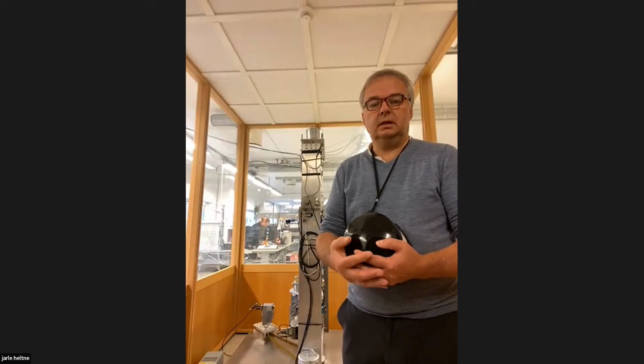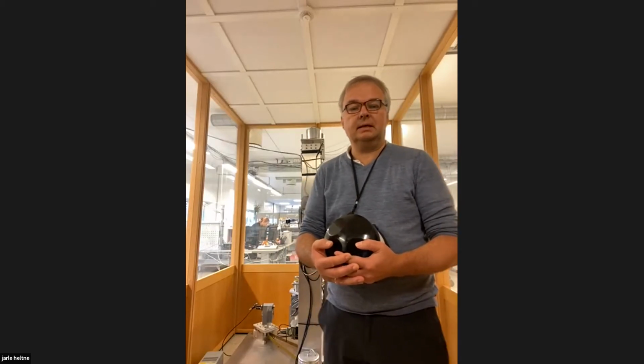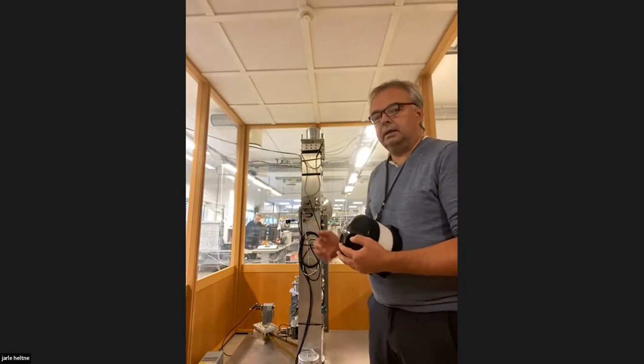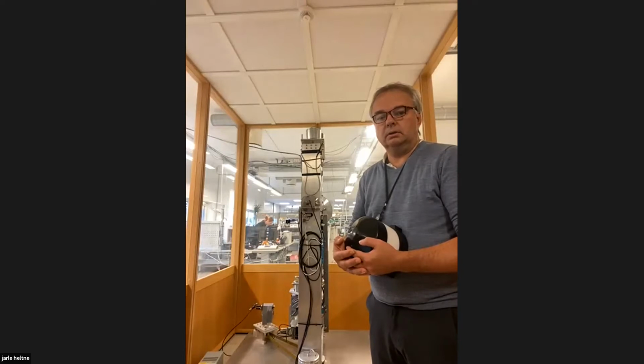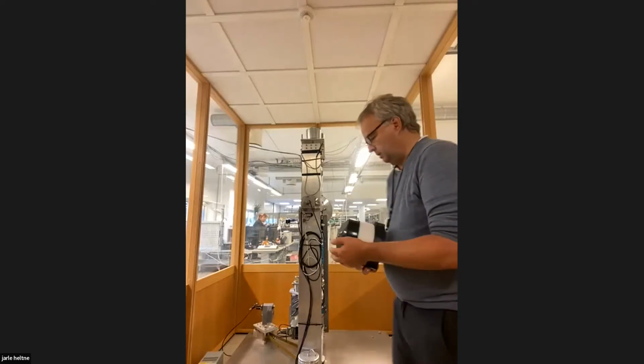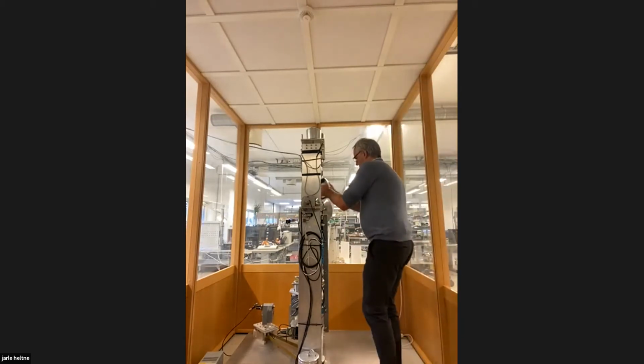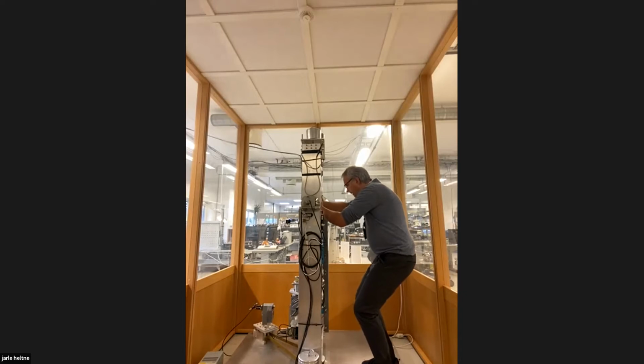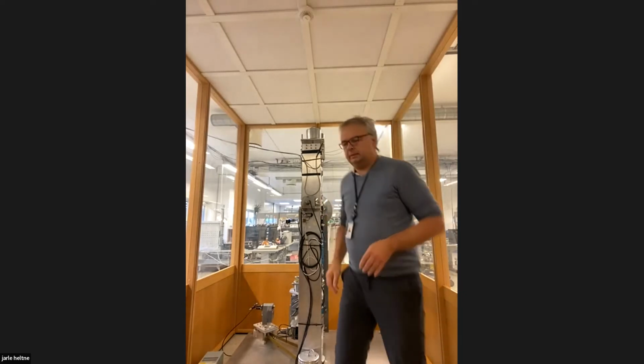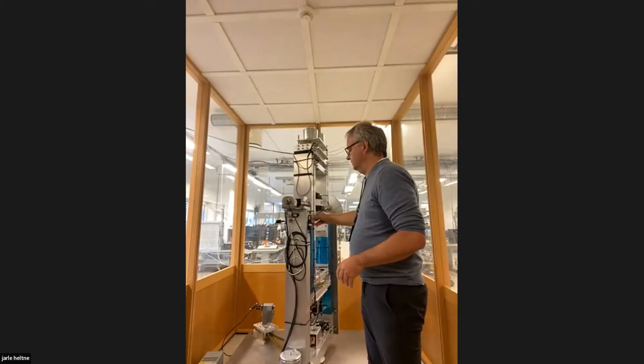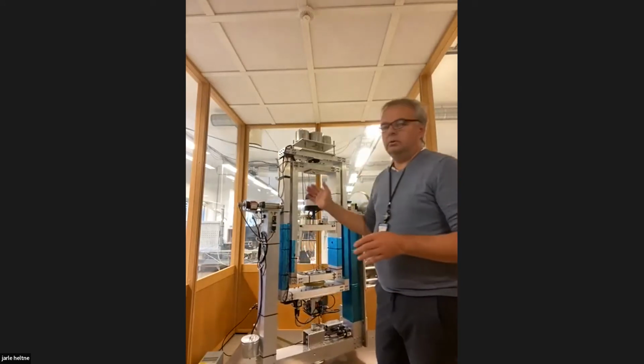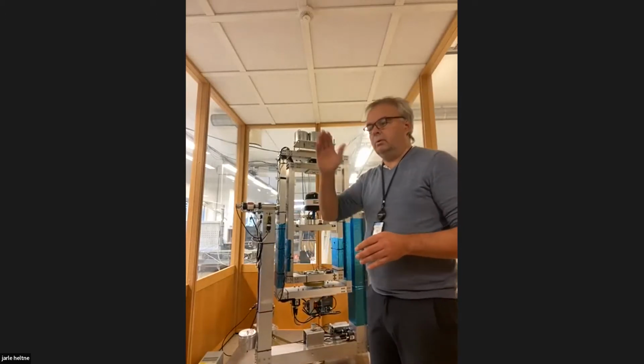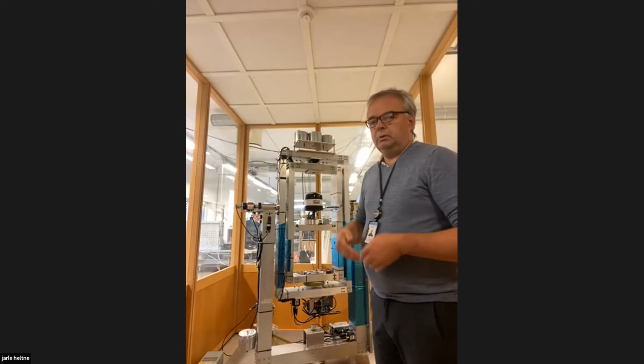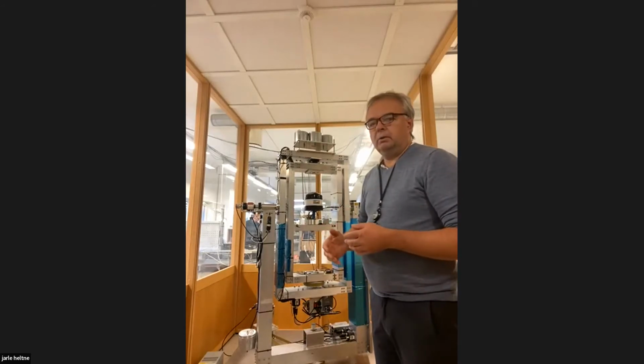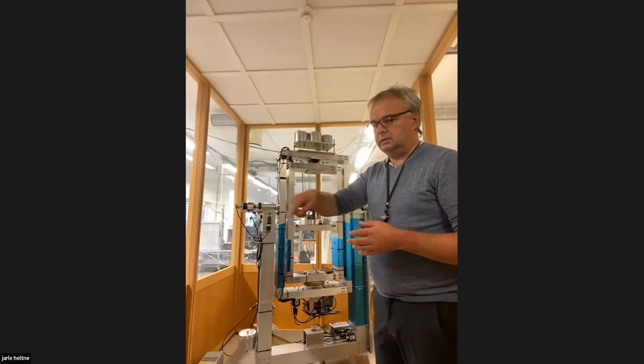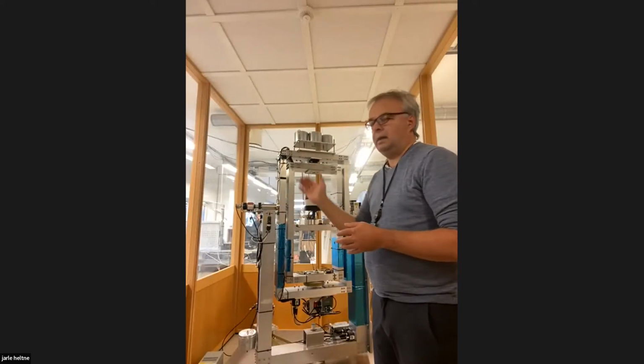Contica room. Contica is short for compass and tilt calibration, and this jig is the one we use for calibrating all our sensors with compass and tilt. I will now put it on the jig. When this sensor is connected to the jig, it turns 360 degrees and does also 40 degrees tilt in all directions. Using this automatic system, we collect a lot of data for every single step around 360 degrees and with 40 degrees tilt.